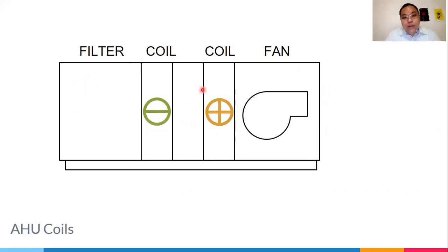Why would you have a heating coil? So that you're able to reach the required humidity conditions of your room, especially when you have low load - for example, your air requirement and your heat load don't match. So this heating coil will give you an artificial load so you can reach your design room conditions.